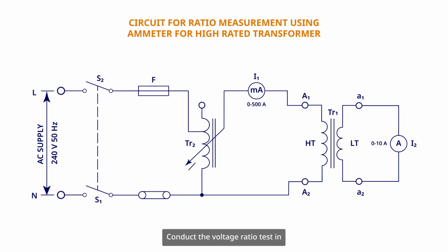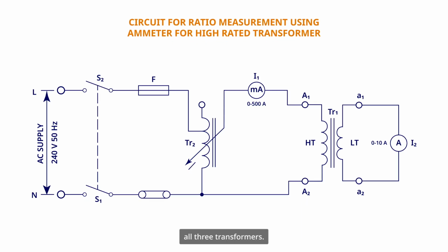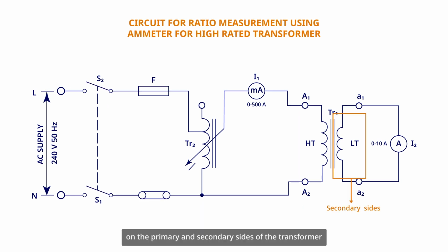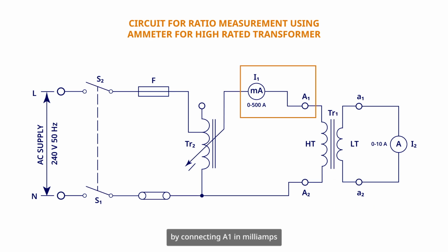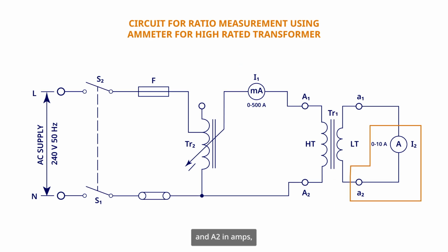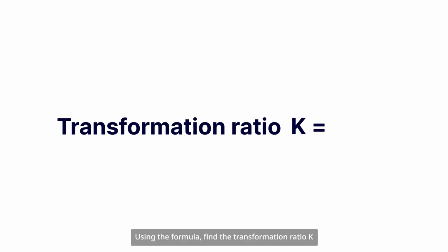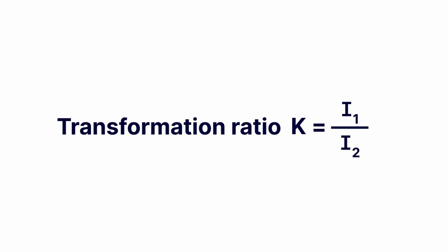Procedure: conduct the voltage ratio test in all three transformers. Measure the current on the primary and secondary sides of the transformer by connecting A1 in milliamps and A2 in amps, respectively. Using the formula, find the transformation ratio K.